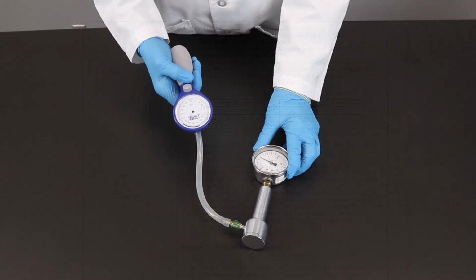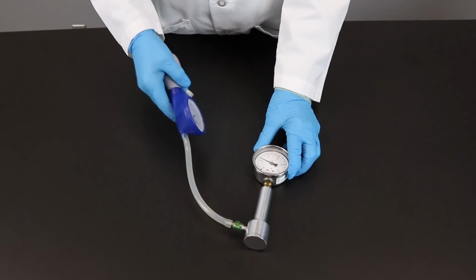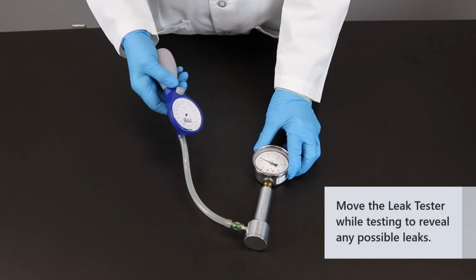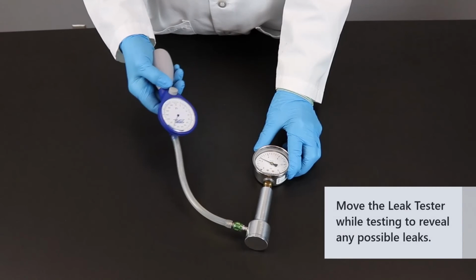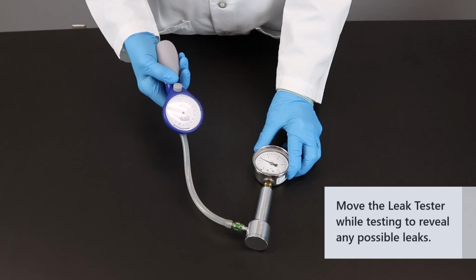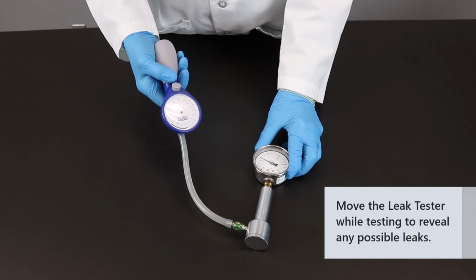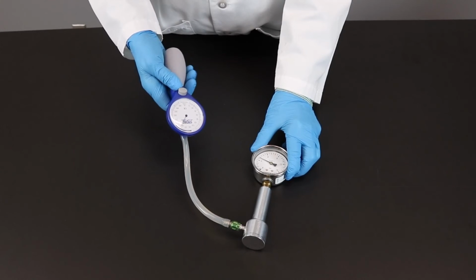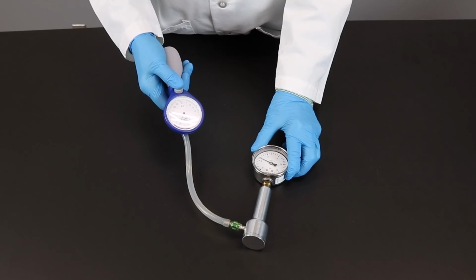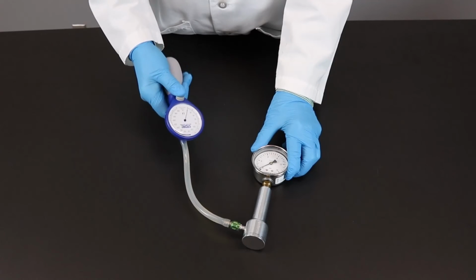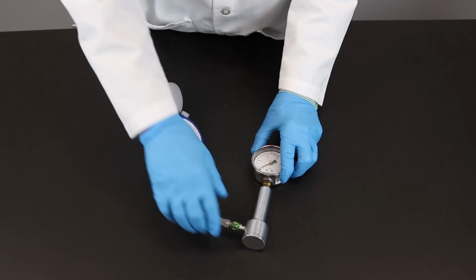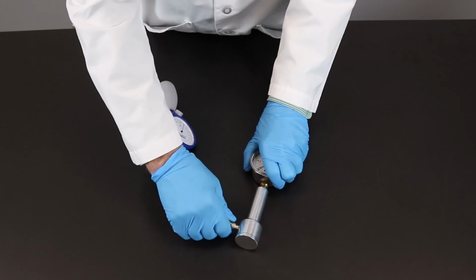As you're performing the leak tester test, you want to move the leak tester a little bit and just make sure that the needle doesn't drop suddenly, meaning that you have a leak or an incomplete connection. At the end of the test, you're going to depress the button on the leak tester to release the pressure and remove it from the leak tester.